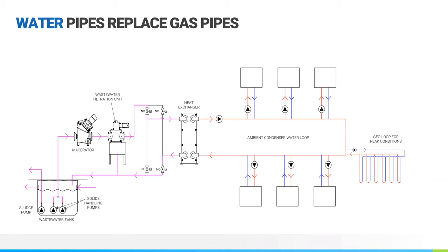Then you've got all your homes and all your schools interconnecting with that district loop, so you're no longer having to drill all the boreholes as your primary heating and cooling, but your geo loop can then provide for your peak cooling and peak heating conditions. And if it's in a super cold or super hot climate, you can throw on a boiler or a potential cooling tower just for those very hot summer days where you may not be able to have that thermal energy transfer from your wastewater or your geo loop conditions.